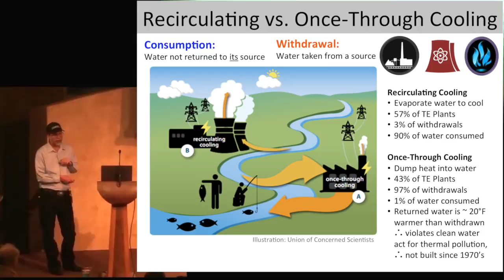You might ask, why don't we just do that — we're not evaporating all that water? Well, it turns out the water can be up to 20 degrees Fahrenheit warmer when returned than when pulled out. By the EPA Clean Water Act, that's defined as thermal pollution. So they haven't built many once-through cooling systems since the 70s because of this problem. Most newer plants use the recirculating approach, which consumes more water — this plant pulls out a lot more water, but they're also returning it.